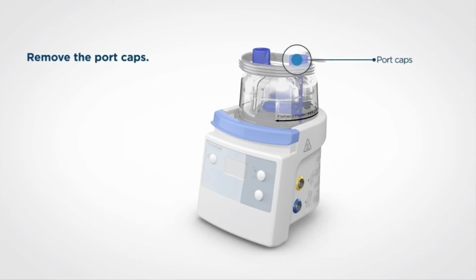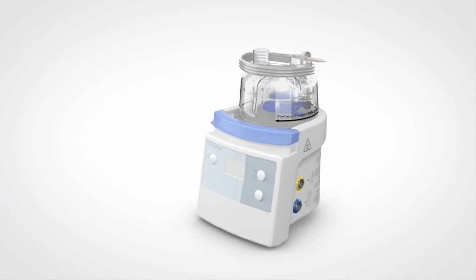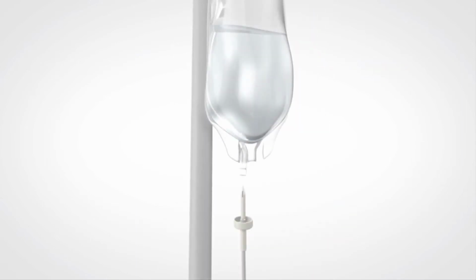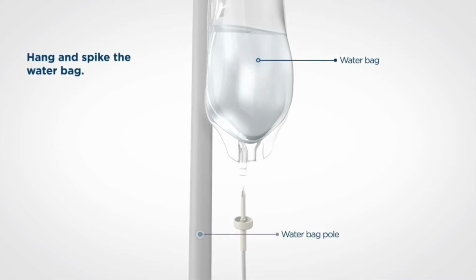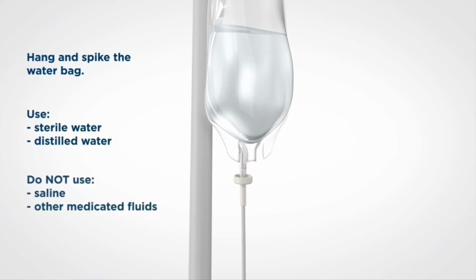There are blue port caps on the top of the chamber that hold the floats in place during transport. Pull up on the ring attached to these port caps, remove and discard them. Under the port caps there is a water feed tube holder. Unwind and remove the water feed tube. If you are ready to use the system immediately, hang a water bag on the water bag pole and spike the water bag. If you're setting up for future use, the water feed set holder can be used to protect and keep the water bag spiked clean. Use sterile or distilled water. Do not use saline or any medicated fluid such as glucose.